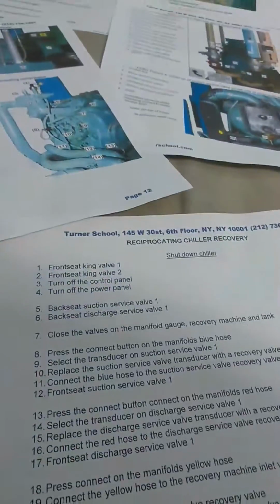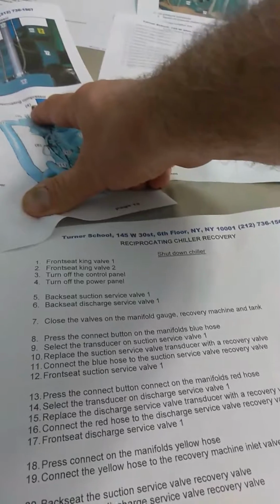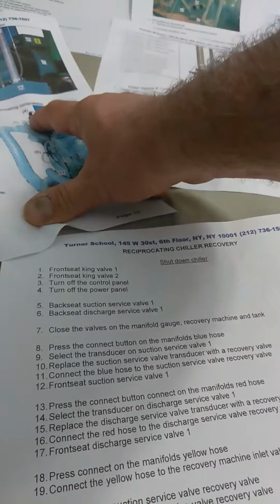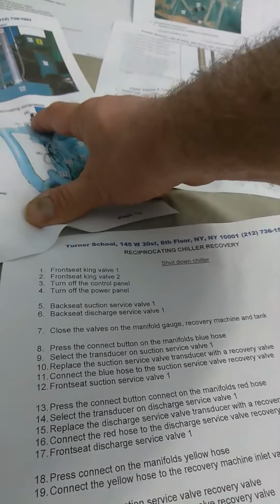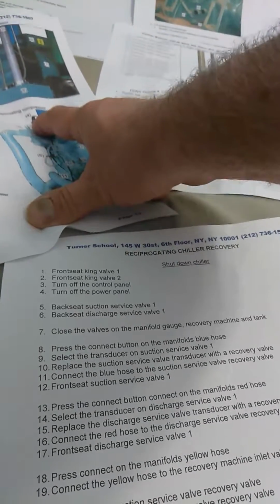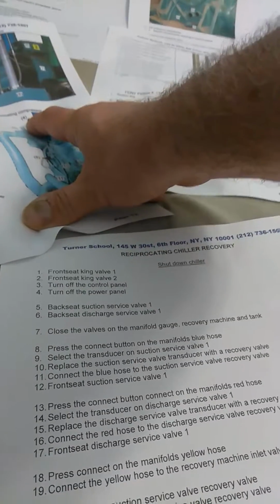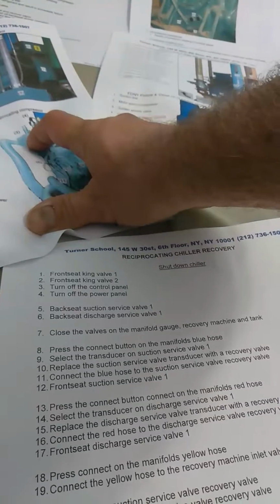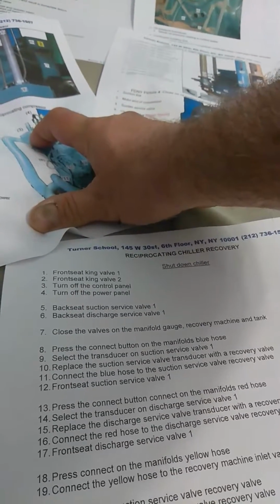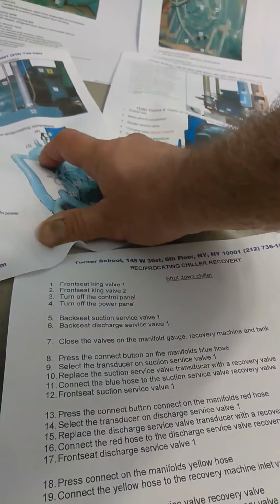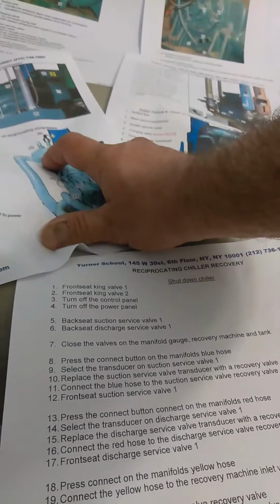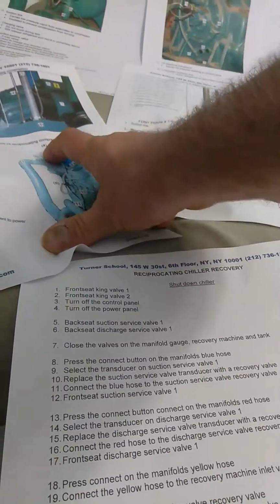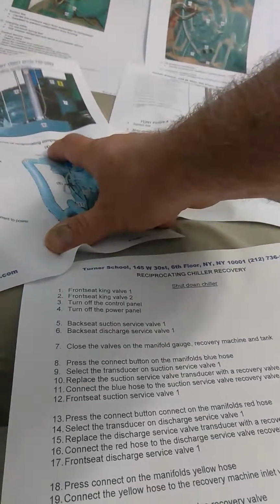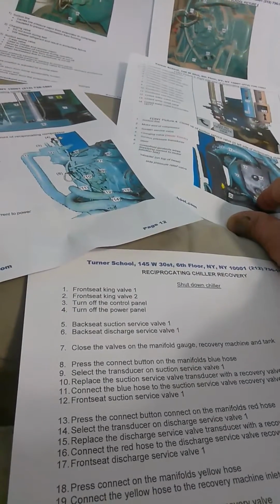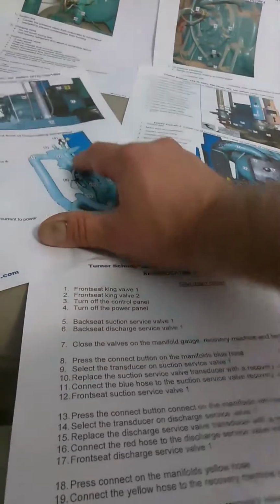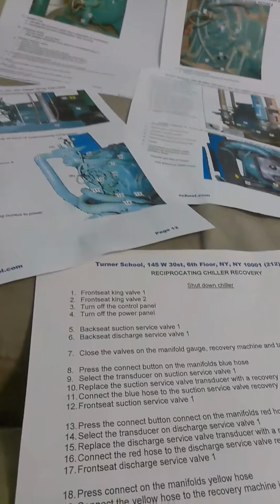Then you go to your discharge side. So select the transducer over here. Change that to a recovery valve. Connect the red hose to the discharge service recovery valve, and then you front seat the discharge service valve. Press the yellow, connect the yellow to the machine. Okay, now you go back to these new recovery valves. Back seat the recovery valve on the suction side. Back seat the recovery valve on the discharge.